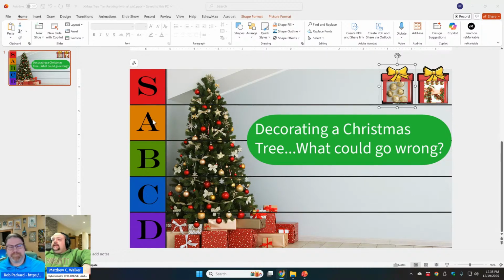Okay. If we were looking at this like a use-related risk analysis, where would we draw the line for a critical task? Right between A and B. If it requires medical attention, it's a 3 or a B, C, D. Those are going to be the ones that you have to report to the FDA, and those are the most serious. Those are also the critical tasks. Critical tasks would be something that will actually result in harm. Whereas the 1s and 2s, those are not something that would require reporting, and they wouldn't be considered a critical task. Okay, I think I understand that.